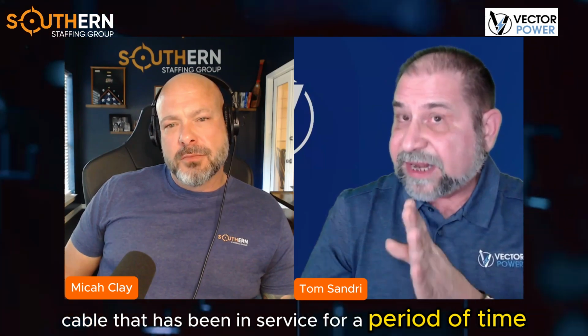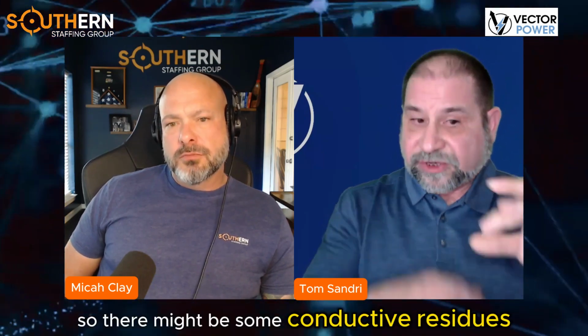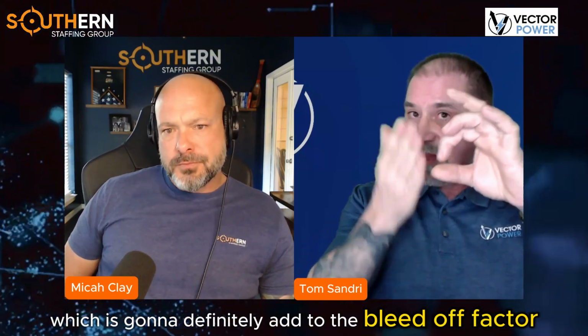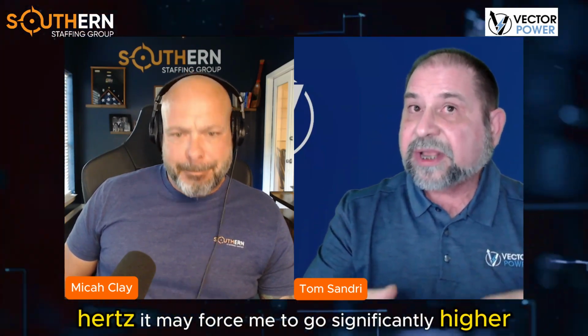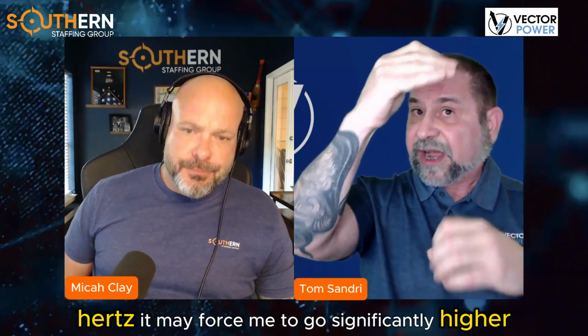Now, with service age cable that has been in service for a period of time, there may have been periods of time where partial discharge was initiated. So there might be conductive residues inside the void, which is going to definitely add to the bleed off factor. So definitely now with those sinusoidal long transitions at 0.1 hertz, it may force me to go significantly higher, in which case my PDIV or inception voltage no longer correlates to the world of 60 hertz.